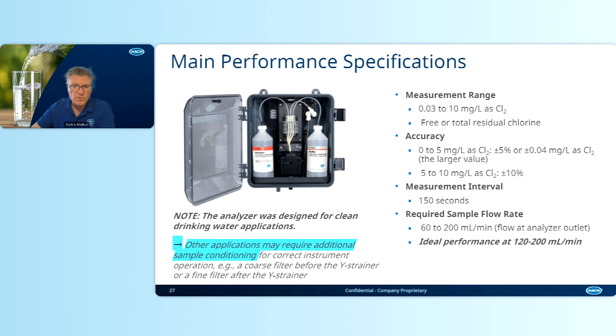Now, the required sample flow rate for the new analyzer is between 60 and 200 mL per minute. It's a little less than was allowed by the old machine. And the ideal performance is achieved at 120 to 200 mL per minute. So the internal flow meter will display that number, and you will always see the flow rate through the analyzer when it's flushing the system.